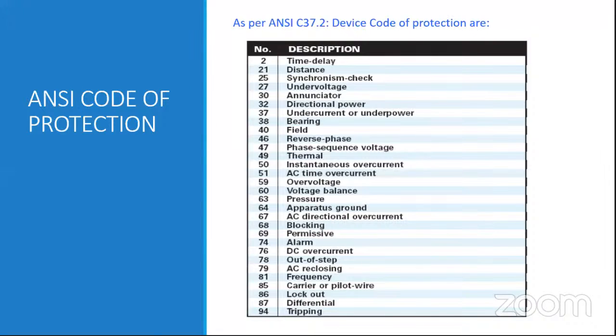Another protection code is 27, which is undercurrent, sorry, under voltage. 30 is the annunciator: if any fault occurs, an alarm is raised at the annunciator. At the annunciator, we should acknowledge that fault, and accordingly it gives an alarm signal to the person to take the necessary actions for this fault condition.